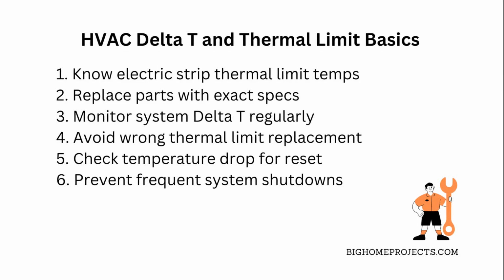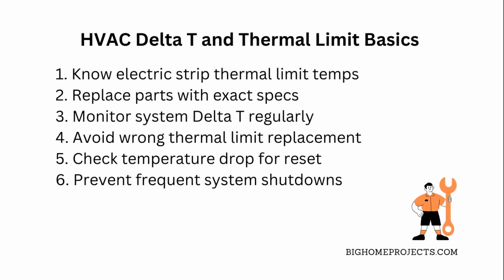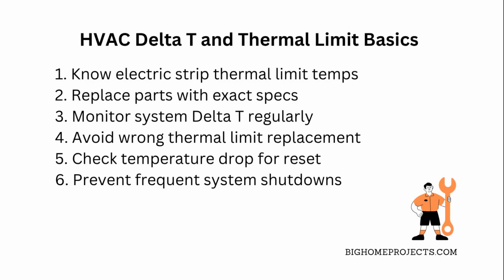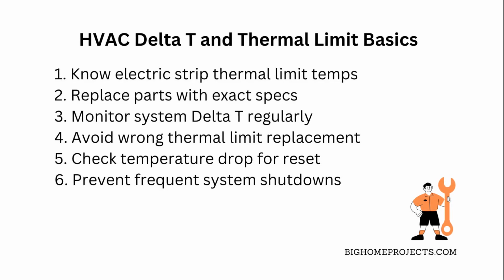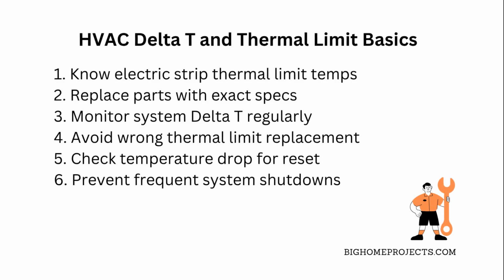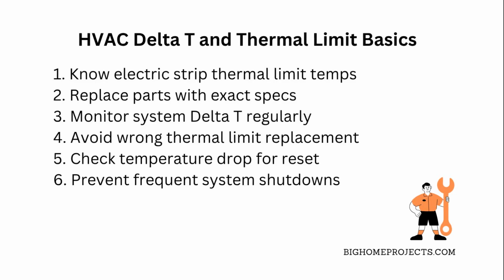Also, keep an eye on your system's Delta T, which is just the temperature difference between the supply and return air. It tells you if your heat exchanger and controls are working right. Running a system with the wrong thermal limit or ignoring Delta T can lead to frequent shutdowns or even system failure. So yeah, double check those temps and specs before swapping parts. It saves you time and headaches.